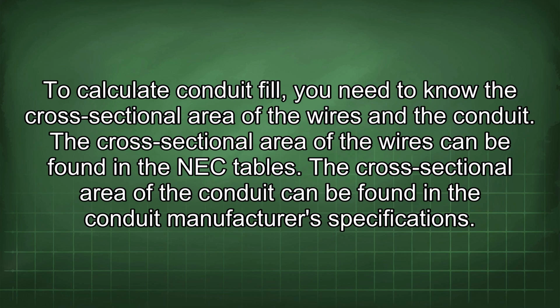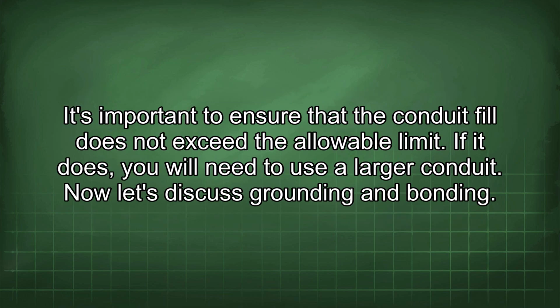To calculate conduit fill, you need to know the cross-sectional area of the wires and the conduit. The cross-sectional area of the wires can be found in the NEC tables. The cross-sectional area of the conduit can be found in the conduit manufacturer's specifications. It's important to ensure that the conduit fill does not exceed the allowable limit. If it does, you will need to use a larger conduit.